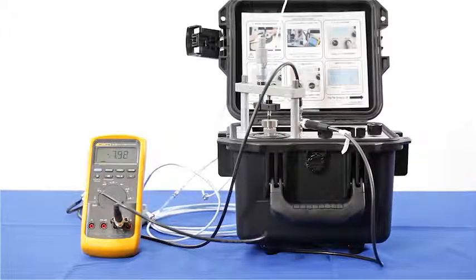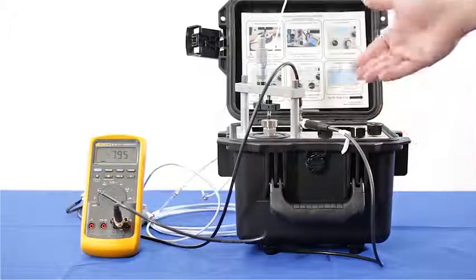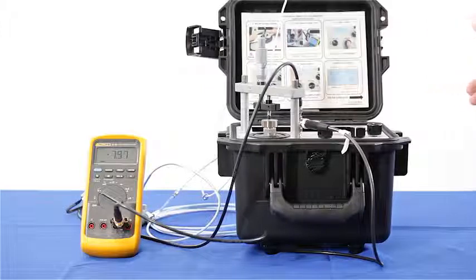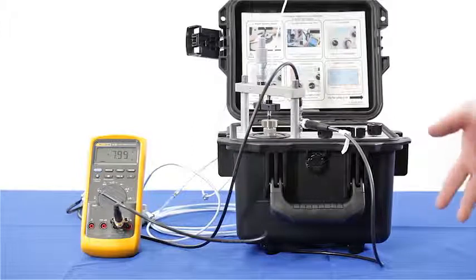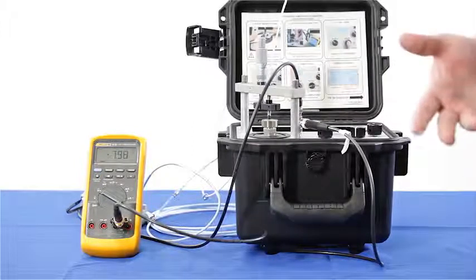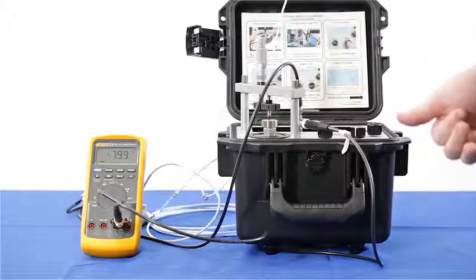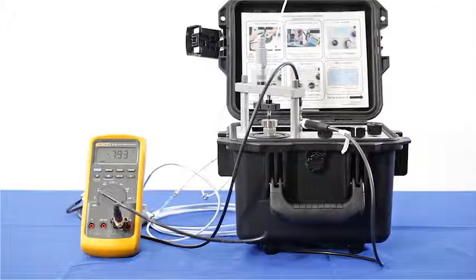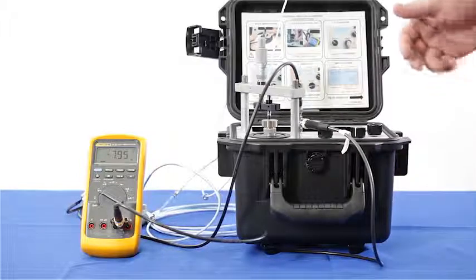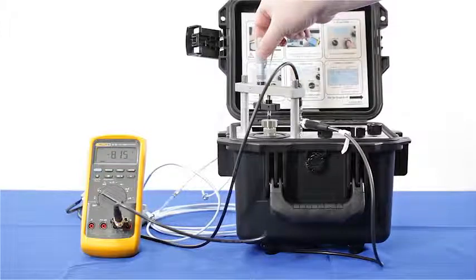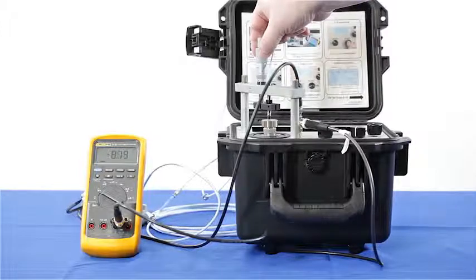Here's where relying upon gap voltage can actually cause increased dynamic output error. You see that my incorrect system here with 5.5 meters of cable has caused the gap voltage to drop to -7.9 volts. It started at -9 volts. So if I walk up to my data acquisition system and press the gap voltage button, it's going to tell me that my gap voltage is a little low. What occurs is the technician may think that the proximity probe is installed incorrectly and actually change the distance, or seemingly change the distance of the probe tip from the center of the shaft, when this is not the problem at all. The problem's been caused by the incorrect cabling.